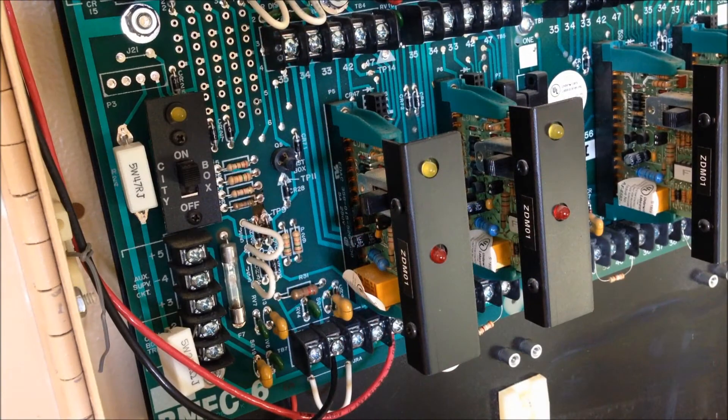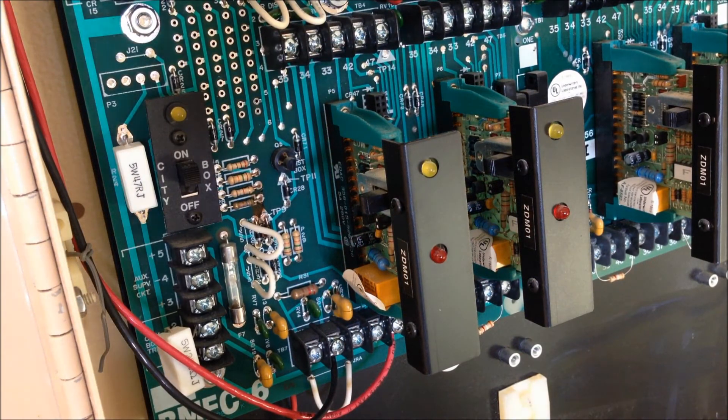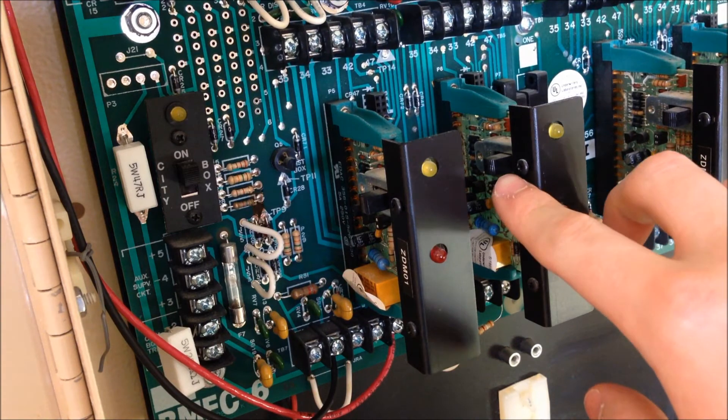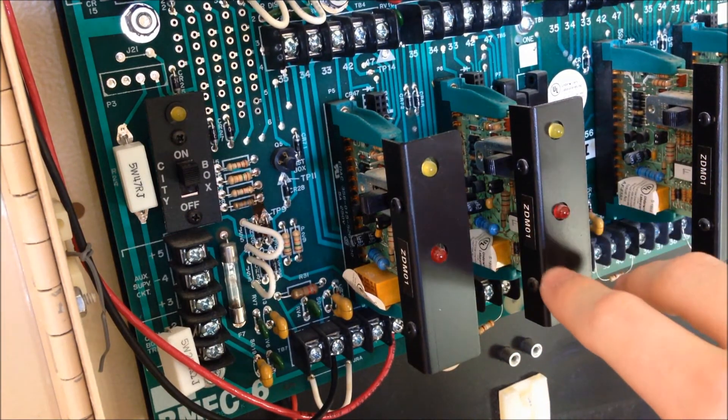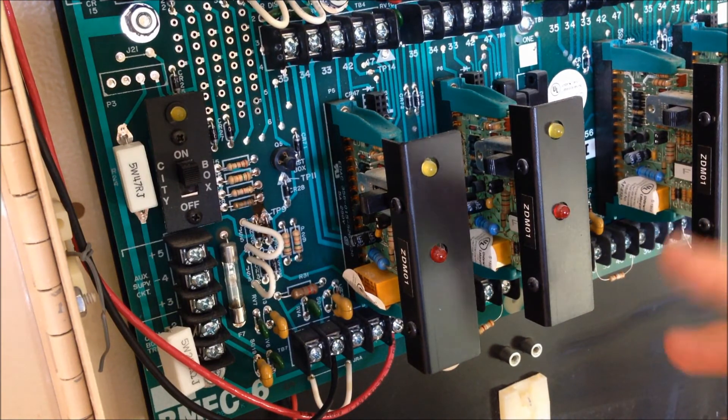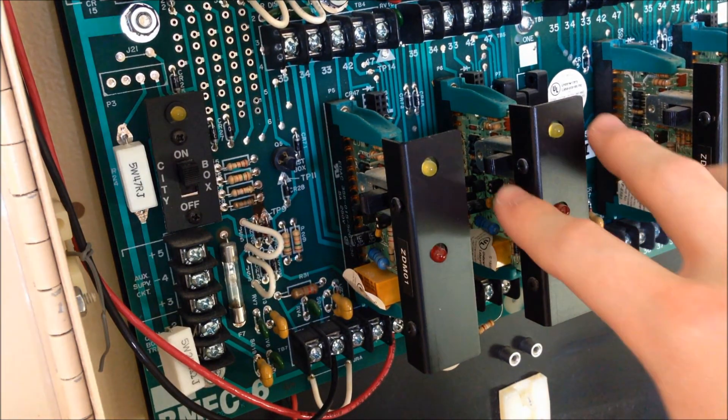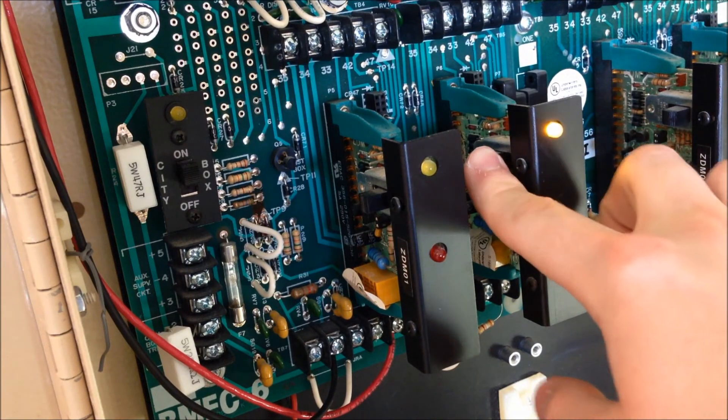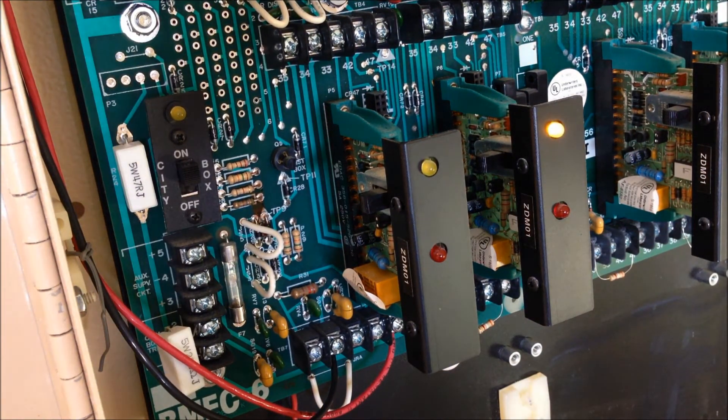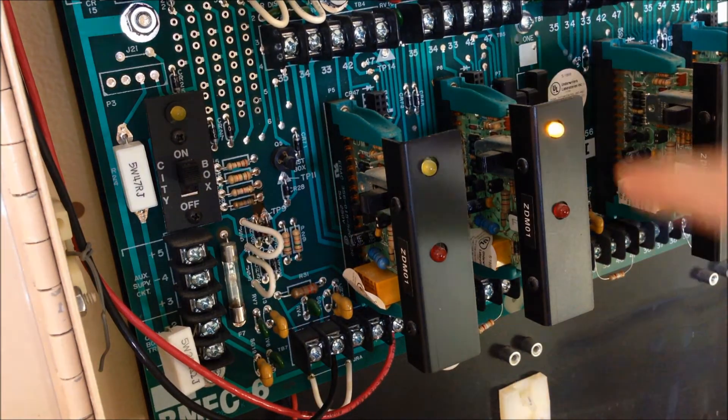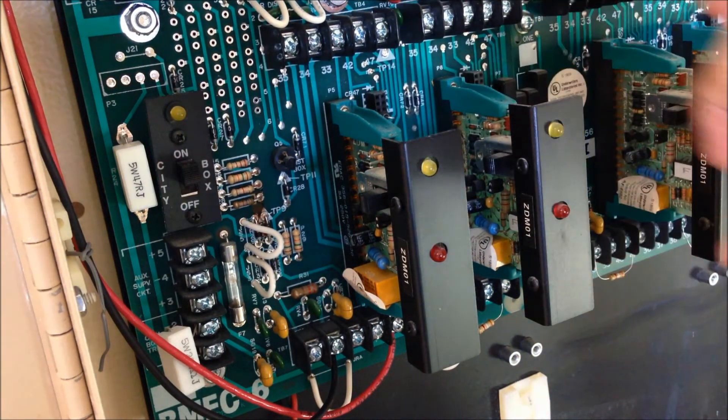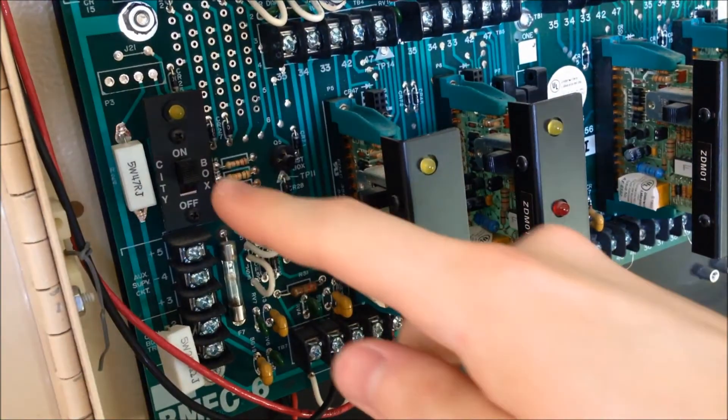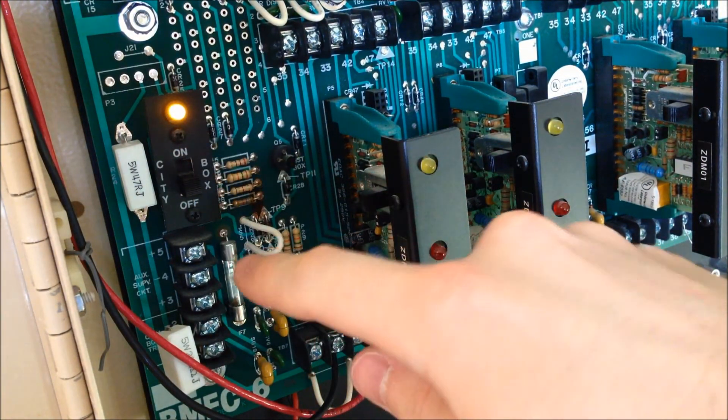Over here you can see some of those switches I was talking about a little bit better. The switches on the side of the zone cards here, like I mentioned they silence the alarms if the alarms originated from the zone. They're also used to bypass the zones so if you turn the switch off you'll get a bypass trouble and you'll see the trouble indicator illuminate on the individual card. You also see we have the city disconnect switch over here which will also cause a trouble.